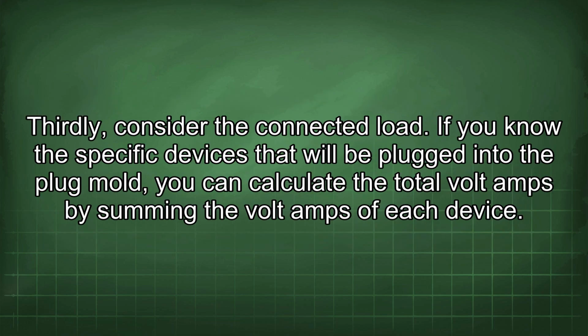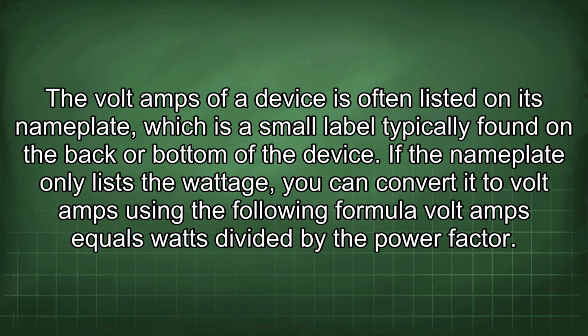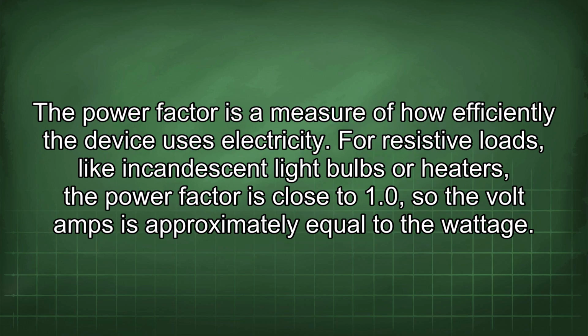Thirdly, consider the connected load. If you know the specific devices that will be plugged into the plug mold, you can calculate the total voltamps by summing the voltamps of each device. The voltamps of a device is often listed on its nameplate, which is a small label typically found on the back or bottom of the device. If the nameplate only lists the wattage, you can convert it to volt amps using the following formula: volt amps equals watts divided by the power factor. The power factor is a measure of how efficiently the device uses electricity. For resistive loads, like incandescent light bulbs or heaters, the power factor is close to 1.0, so the voltamps is approximately equal to the wattage.